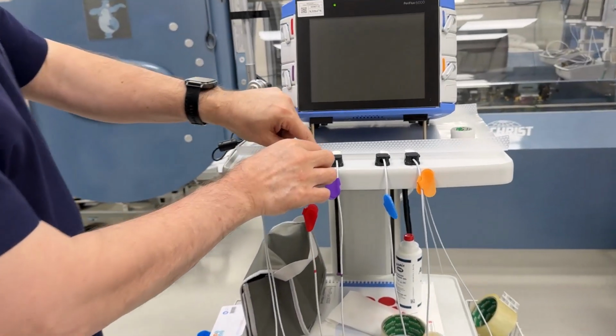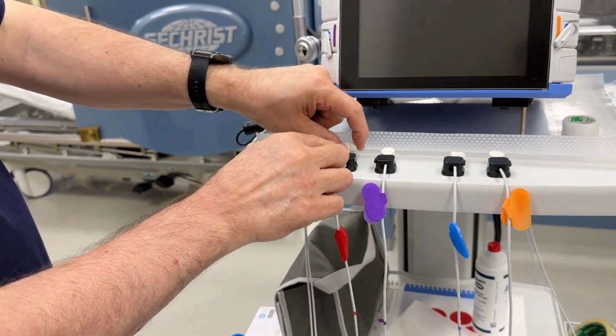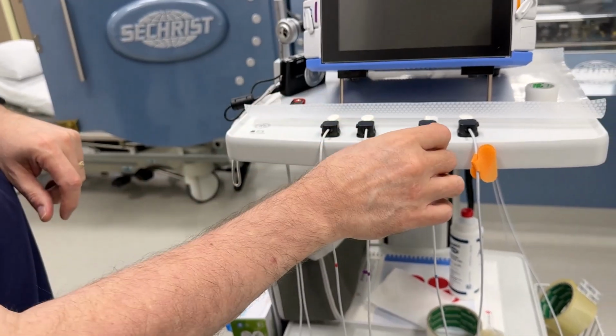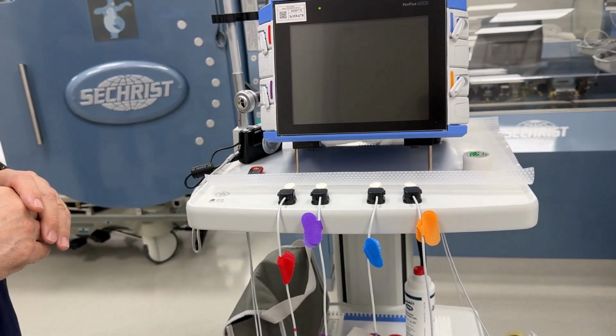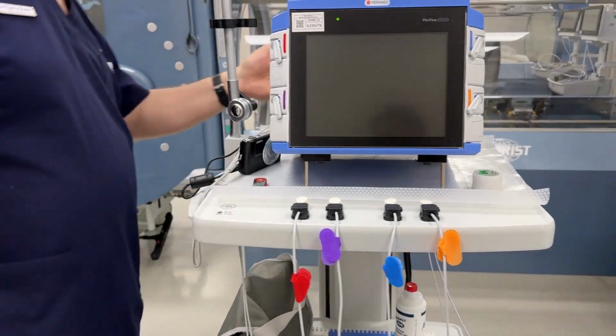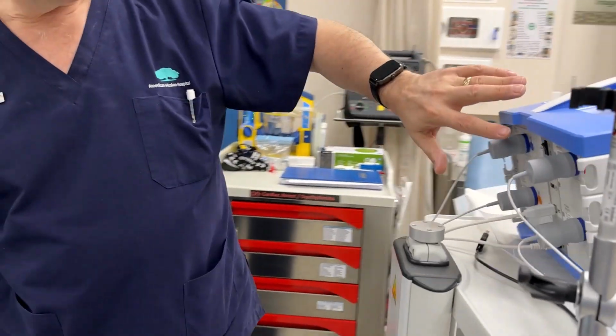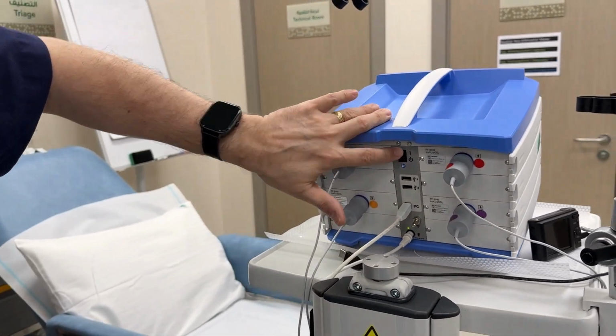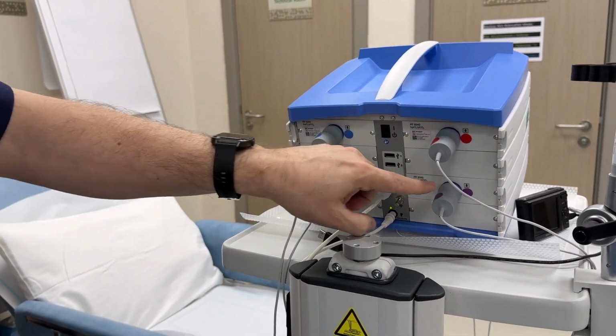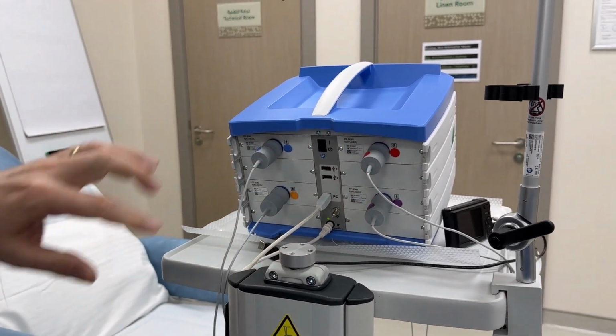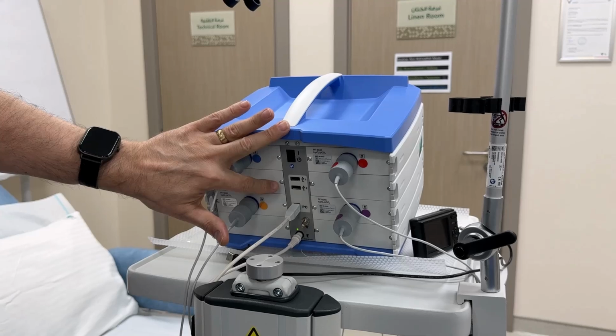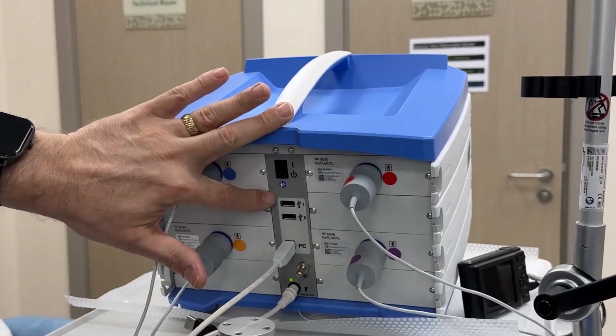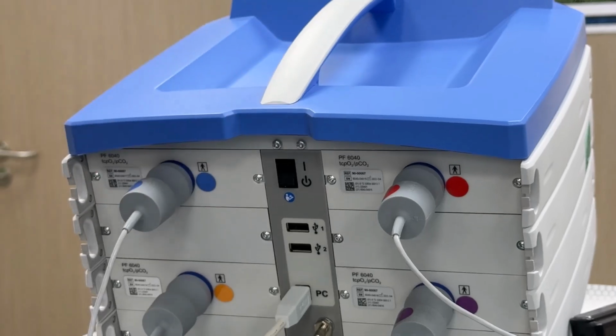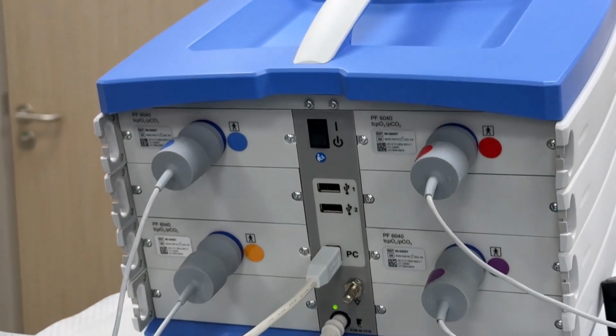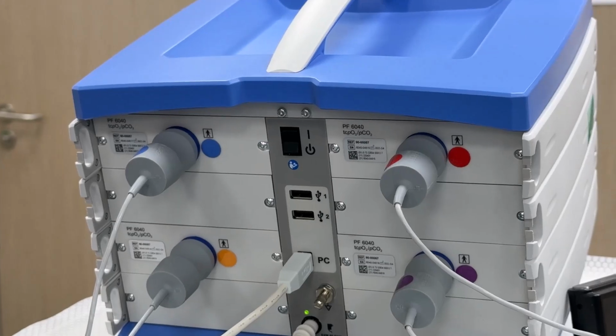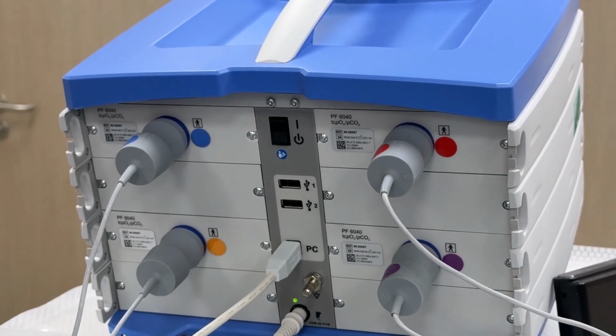The electrodes are kept with their caps on, and there is fluid left in the caps to make sure that the membranes don't dry out. So the first step at the back is to turn on the machine and to ensure that all 4 electrode plugs are in place. You'll notice that there are 2 USB slots. The upper or first USB slot is used both to load an image of the wound and sites, as well as to download the report once that has been completed.